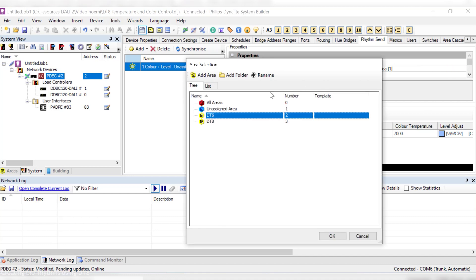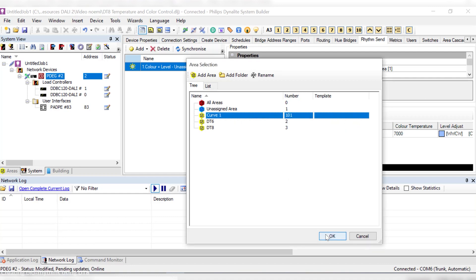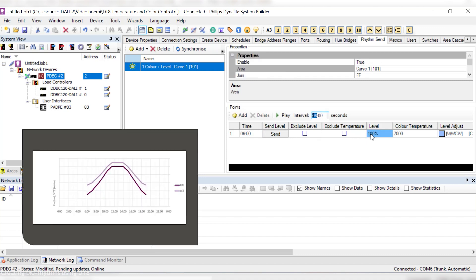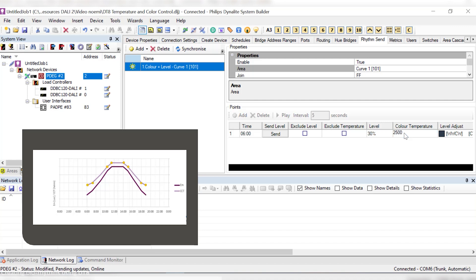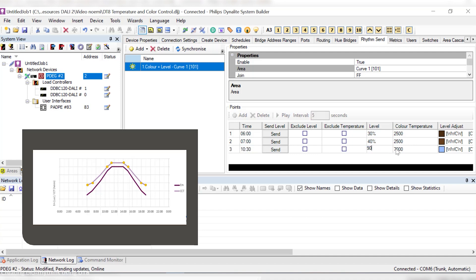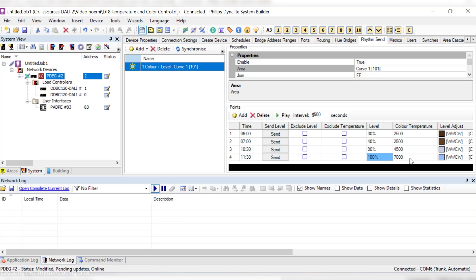In this case, we'll select the first option and create a dummy area that will represent our curve. In projects with multiple floors, we could use a common area for sharing the rhythm among all of them. If needed, set a join mask. What we'll do next is creating points specifying the time, the level, and the color temperature that corresponds to the curve we'd like to create. In my case, I'm using a curve similar to this, where the y-axis represents the color temperature in Kelvin, and the x-axis represents the 24 hours of the day. Basically, the curve will make a transition between 8 points. For example, at 6 AM, it will start with 30% and 2,500 Kelvin, and slowly increase to 40% by 7 AM. From there, it will make a bigger change ramping up to 90% and 4,500 Kelvin by 10:30. The transitions between points are slow so that they are not perceived.